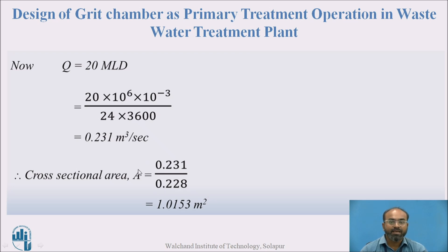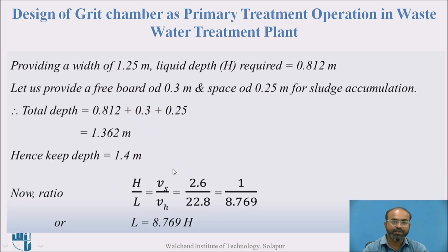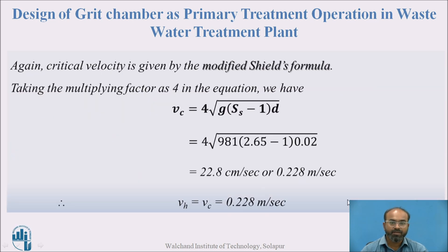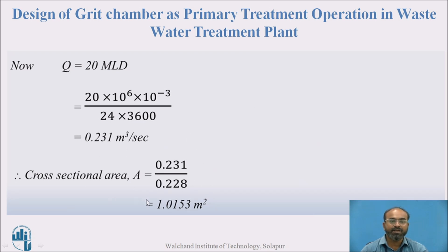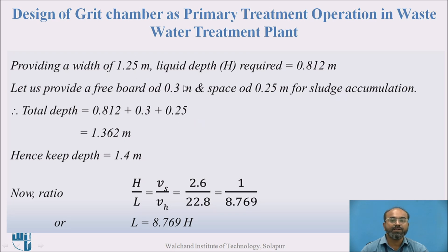Using Q = A × V, cross-sectional area A = Q / V = 0.231 / 0.228 ≈ 1.0153 m². Providing a width of 1.25 m, the required liquid depth H = 0.812 m. Adding a freeboard of 0.3 m and 0.25 m for grit accumulation, the total depth becomes 0.812 + 0.3 + 0.25 = 1.362 m, which we round up to 1.4 m.